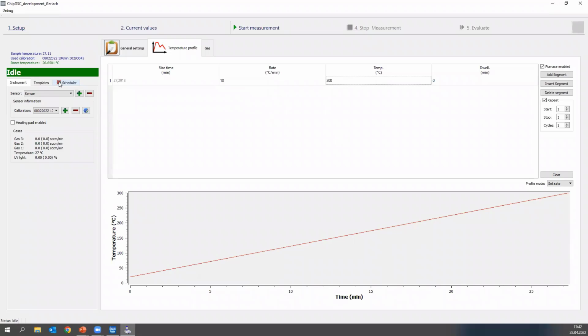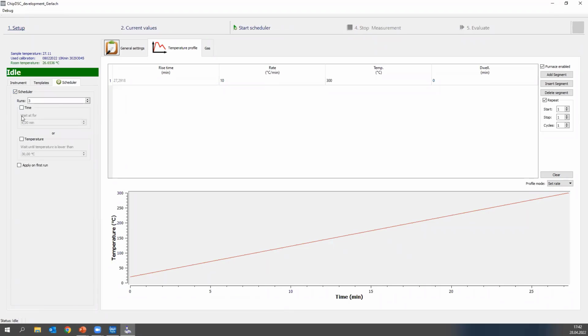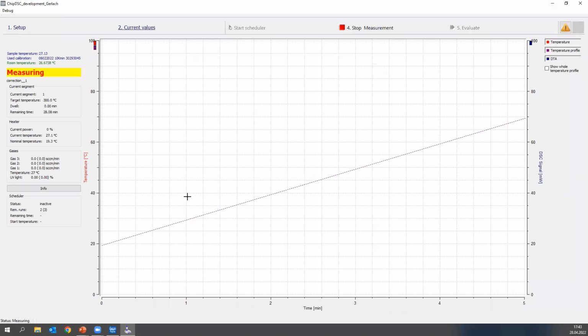What I also do for correction curves and calibration curves is use a scheduler. I just tell the software to run this measurement 3 times until you reach a temperature of, for example, 30 degrees Celsius, and the software automatically starts again at 30 degrees Celsius. I do this 3 times so I can make sure nothing affects the measurement, like someone who went into the lab, or some radiation through sunlight, or things like this that could affect our measurement. For this reason, I'm using the scheduler, and then I can click start, and that's it.